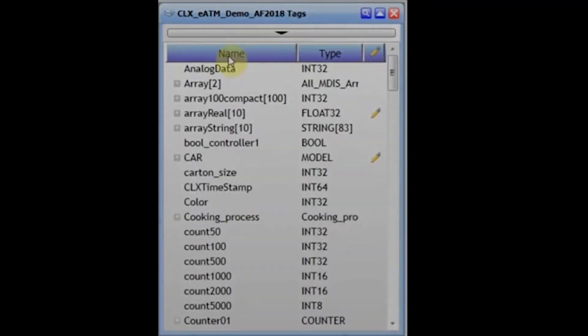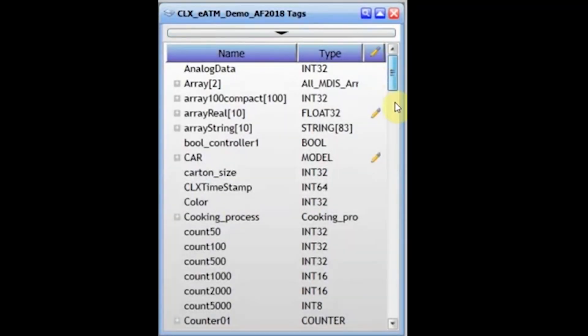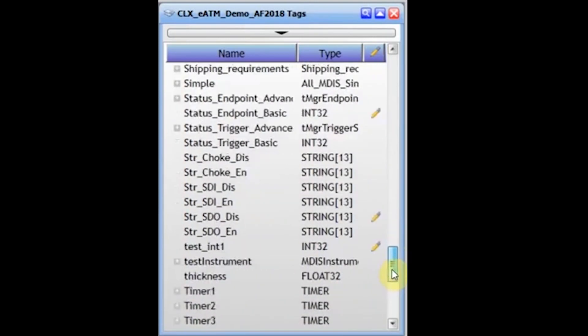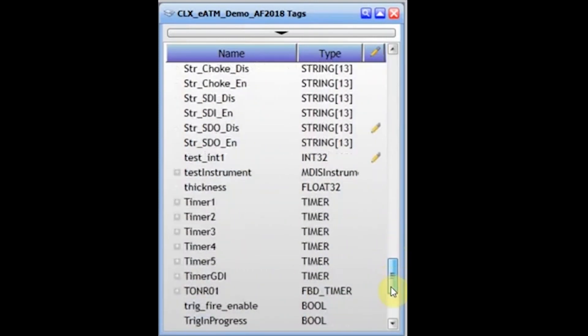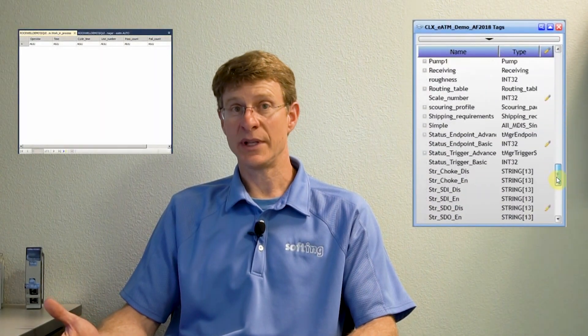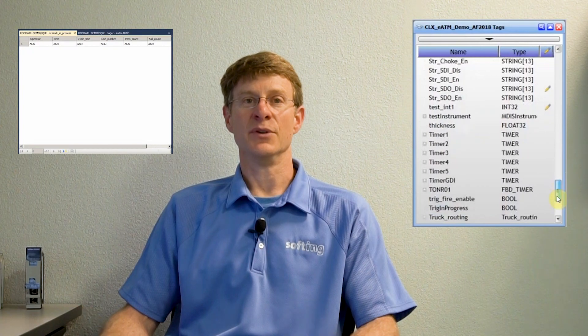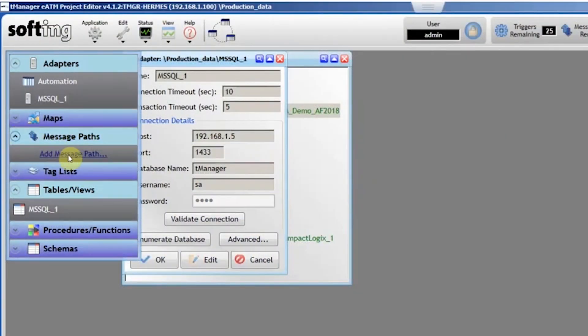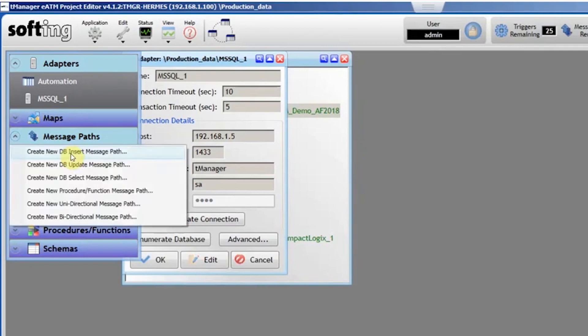On the control system side, you're going to create your logic with writable tags. You don't need to create 10 recipes in the PLC — you just need to create one logic set with writable tags. With your tag variables created in the PLC and your table created in the SQL database, the only thing left to do is to map the SQL table to the PLC tags in what's called a message path.